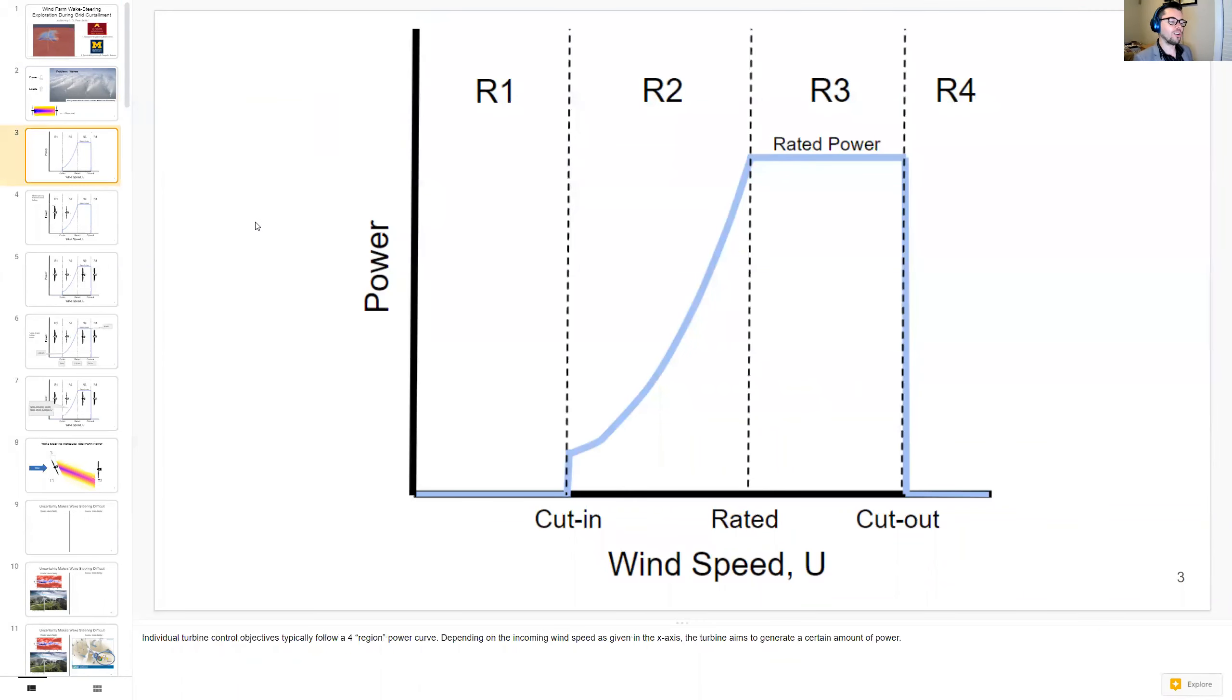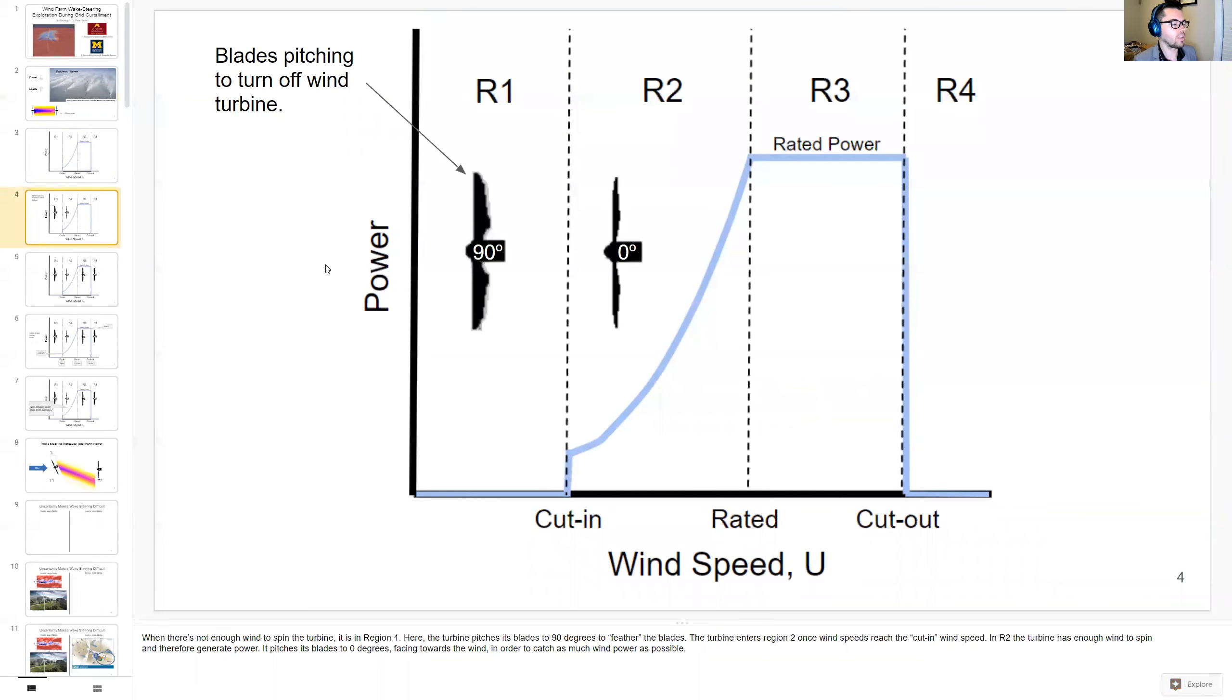Individual turbine control objectives typically follow a four-region power curve. Depending on the incoming wind speed as given on the x-axis, the turbine aims to generate a certain amount of power as given on the y-axis. When there's not enough wind to spin the turbine, it is in region 1. Here the turbine pitches its blades to 90 degrees to feather the blades.